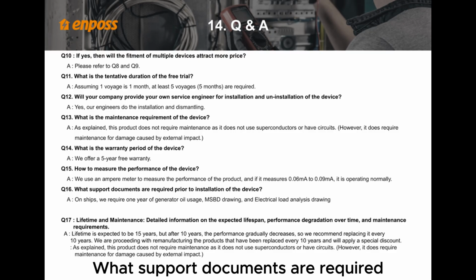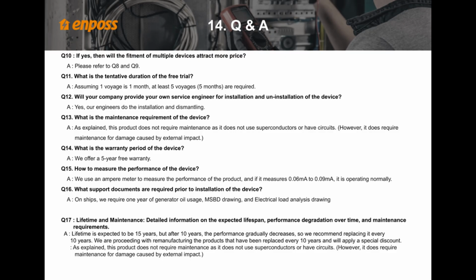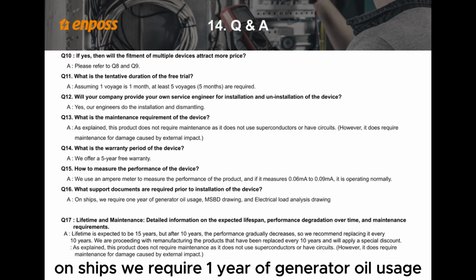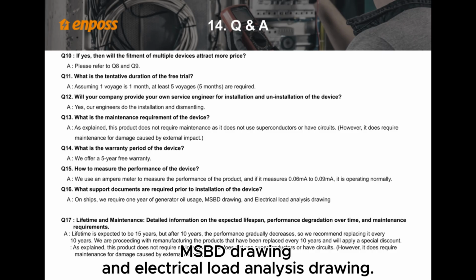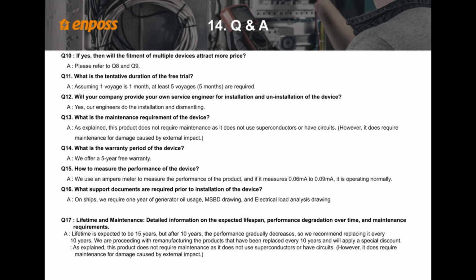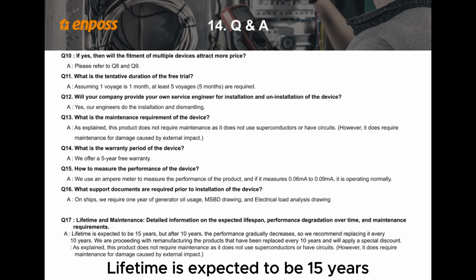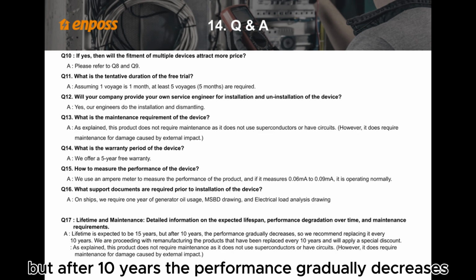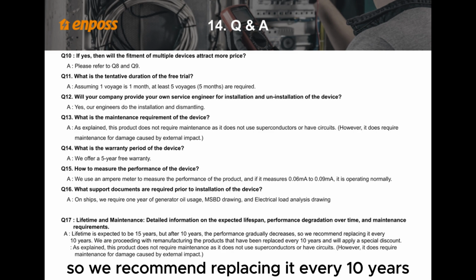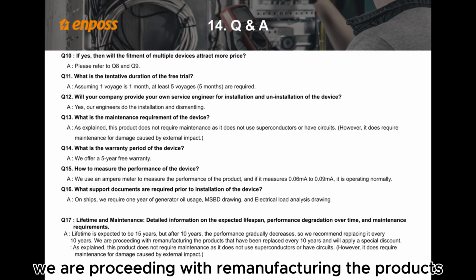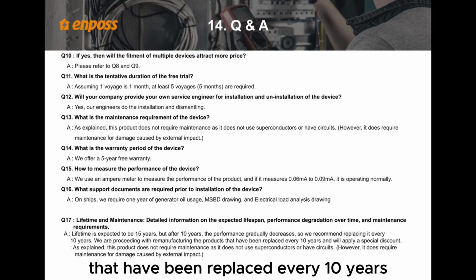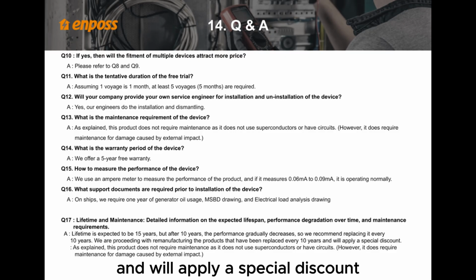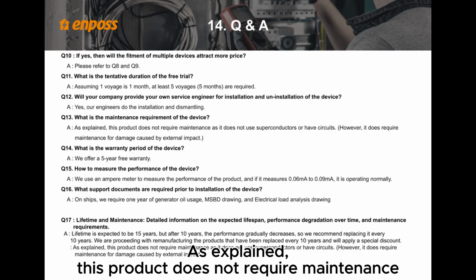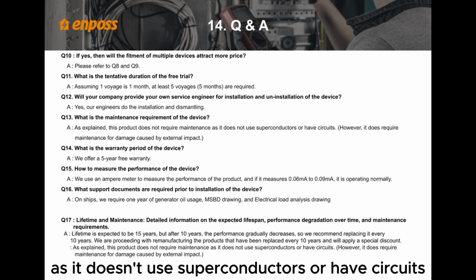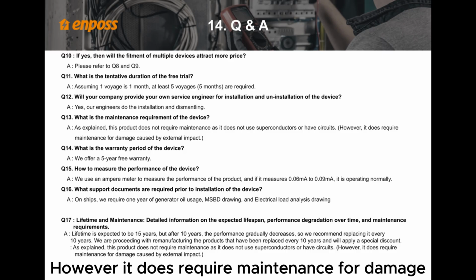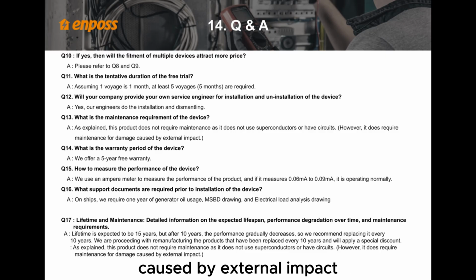What support documents are required prior to installation of the device? On ships, we require 1 year of generator oil usage, MSBD drawing, and electrical load analysis drawing. Lifetime and maintenance. Lifetime is expected to be 15 years, but after 10 years the performance gradually decreases, so we recommend replacing it every 10 years. We are proceeding with remanufacturing the products that have been replaced every 10 years and will apply a special discount. As explained, this product does not require maintenance as it does not use superconductors or have circuits. However, it does require maintenance for damage caused by external impact.